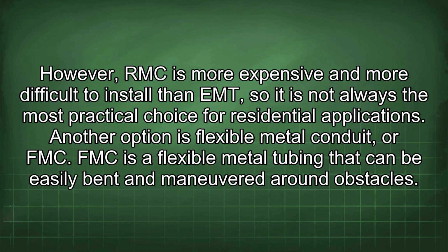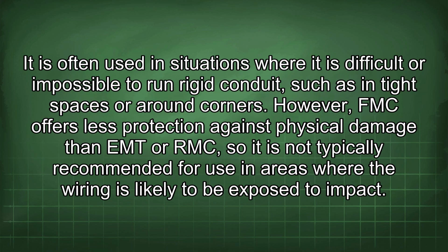However, RMC is more expensive and more difficult to install than EMT, so it is not always the most practical choice for residential applications. Another option is flexible metal conduit, or FMC. FMC is a flexible metal tubing that can be easily bent and maneuvered around obstacles. It is often used in situations where it is difficult or impossible to run rigid conduit, such as in tight spaces or around corners. However, FMC offers less protection against physical damage than EMT or RMC, so it is not typically recommended for use in areas where the wiring is likely to be exposed to impact.